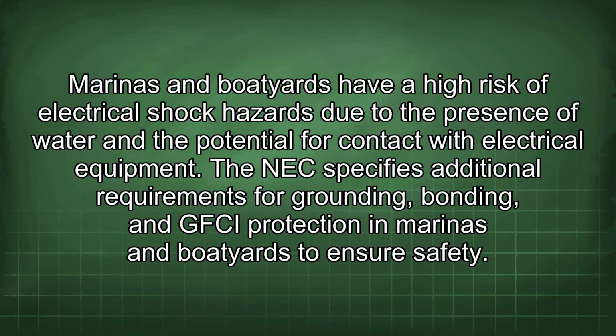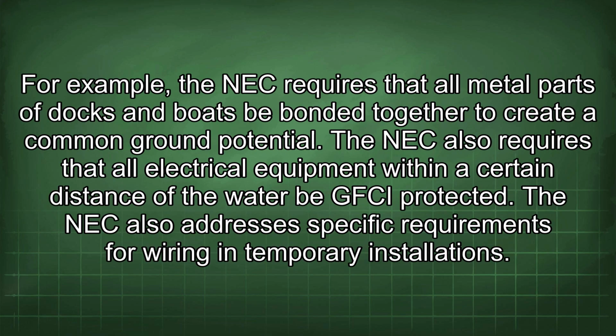The NEC specifies additional requirements for grounding, bonding, and GFCI protection in marinas and boatyards to ensure safety. For example, the NEC requires that all metal parts of docks and boats be bonded together to create a common ground potential. The NEC also requires that all electrical equipment within a certain distance of the water be GFCI protected.